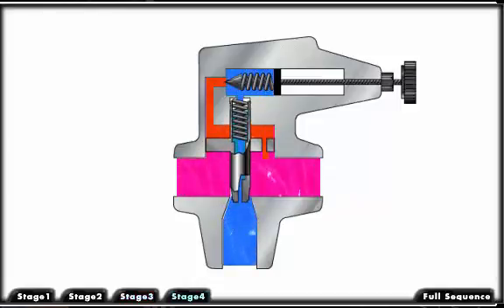This restricted flow caused by the orifice creates a pressure difference between the pump line and the area across the pilot orifice. This pressure imbalance causes the main poppet to move off its seat. This will discharge enough of the pump flow to prevent any further rise in the pump line pressure.